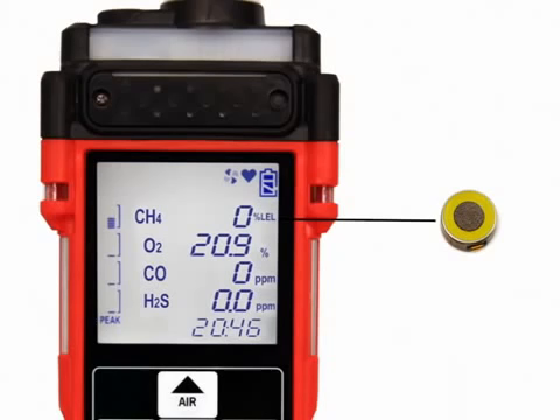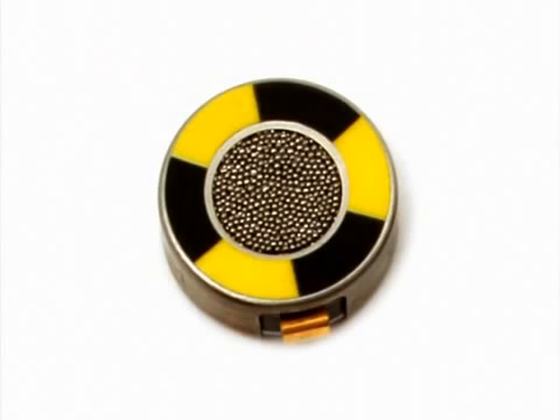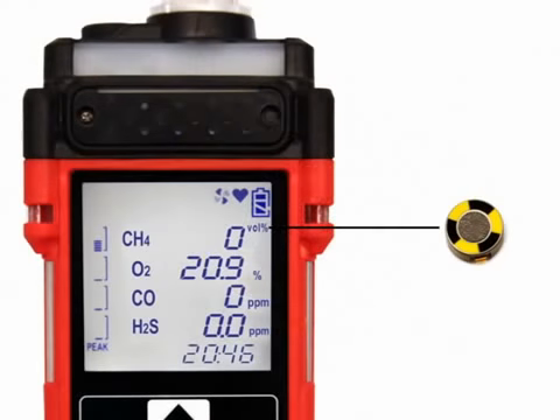the LCD. The percent volume combustible gas sensor detects methane in the percent volume range with a thermal conductivity element. It is not always installed in the GX 2012. The reaction of gas with the sensor cools the active element and causes a change in the resistance of the element, which affects the current flowing through it.